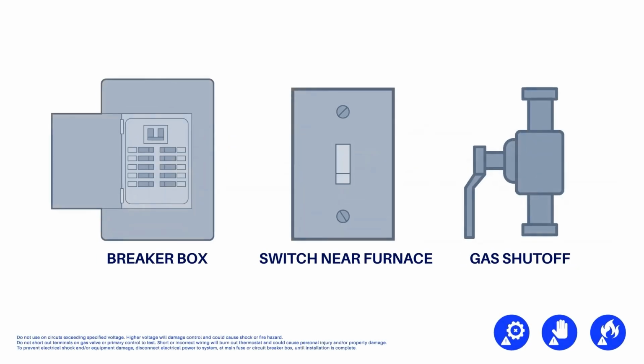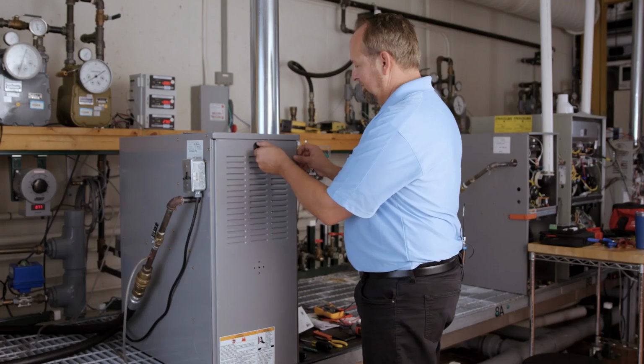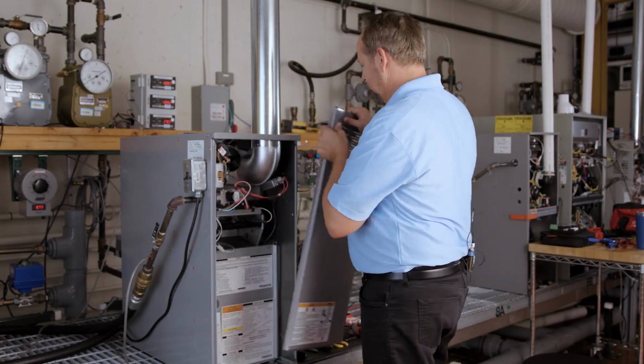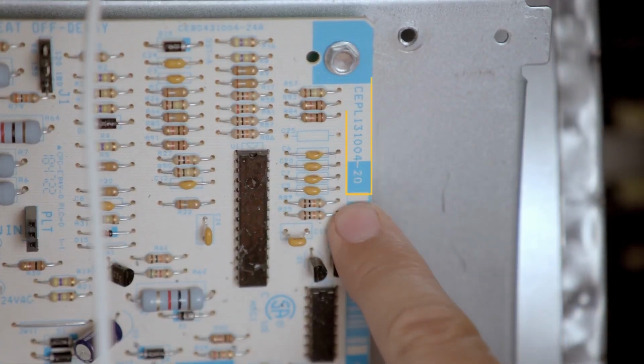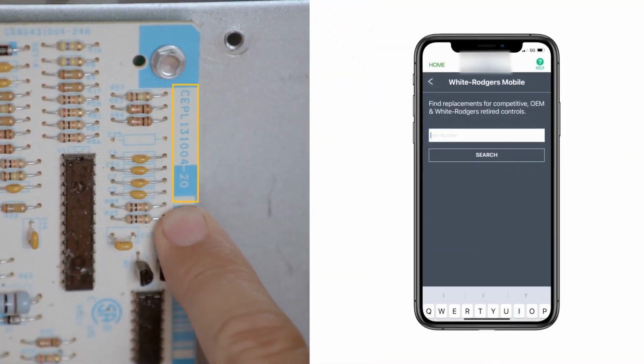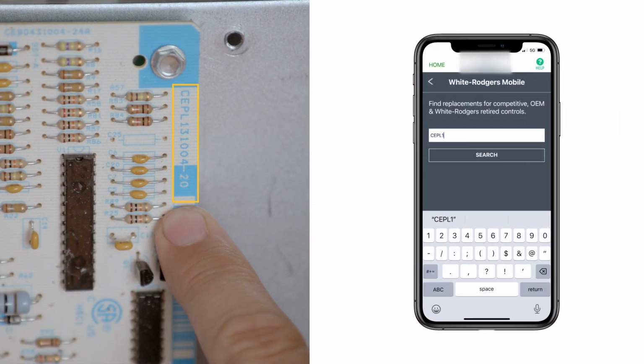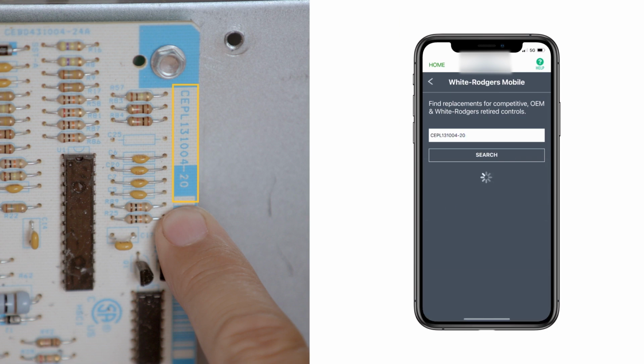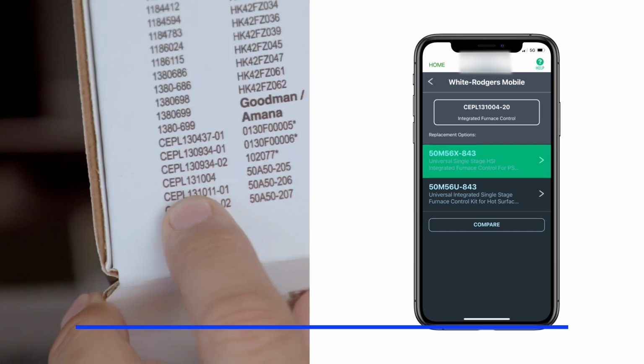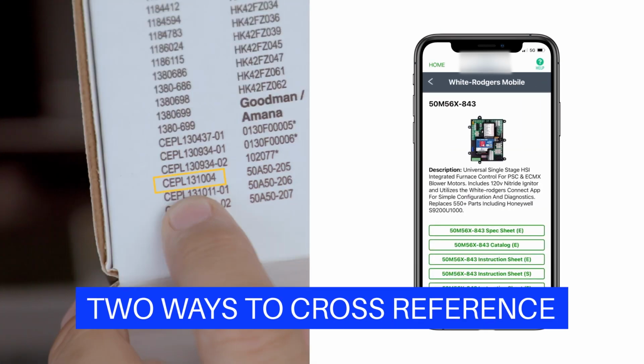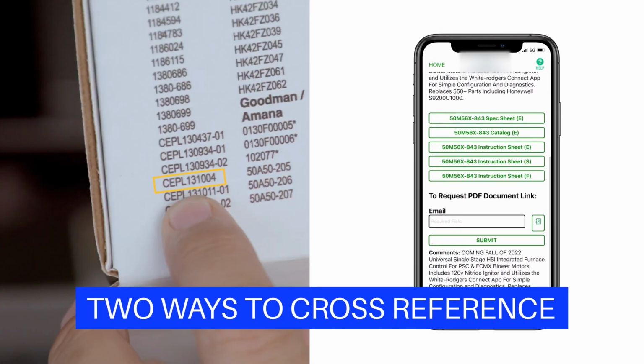First, ensure power and gas are disconnected prior to servicing the unit. Remove the unit access panel. Check the part number on the existing control and verify it is one of the more than 550 modules that can be replaced with the 50M56X-843. Use the cross-reference chart on the side of the carton or the White-Rodgers mobile app.